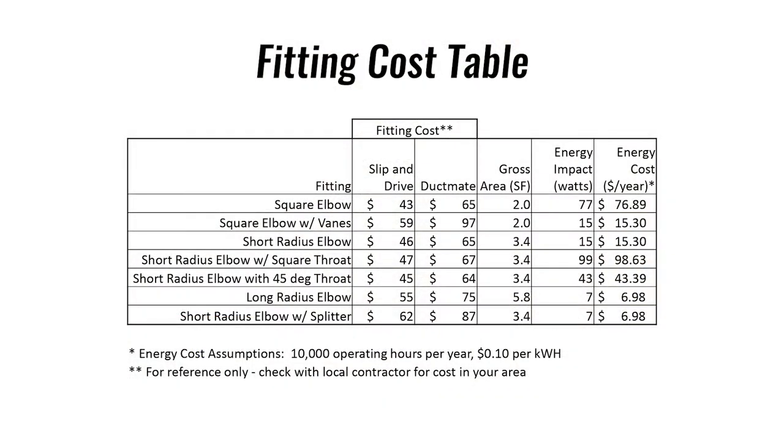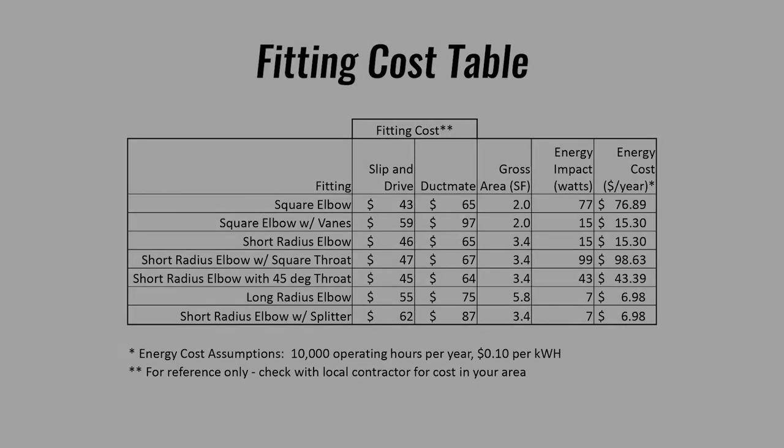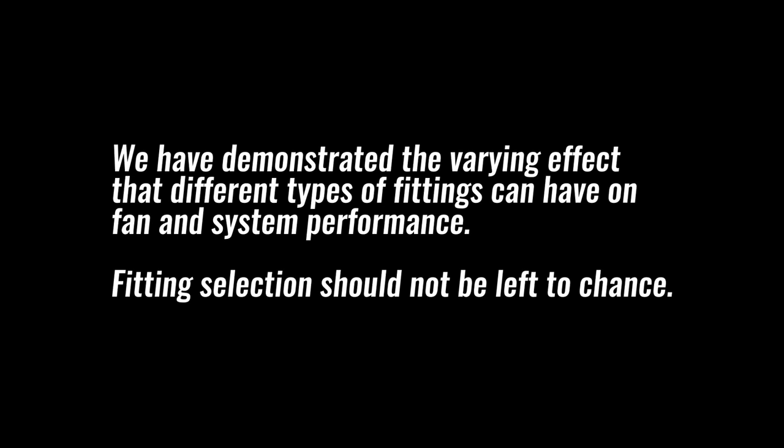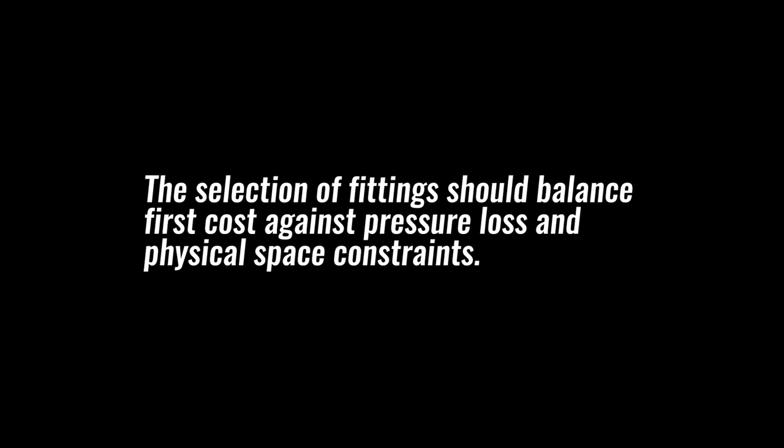This table of fitting is shown as a template for you to make your own comparisons. Cost of fabrication and electricity can vary from location to location. Summarizing, we have demonstrated the varying effect that different types of fittings can have on fan and system performance. Fitting selection should not be left to chance. The selection of fittings should balance first cost against pressure loss and physical space constraints.